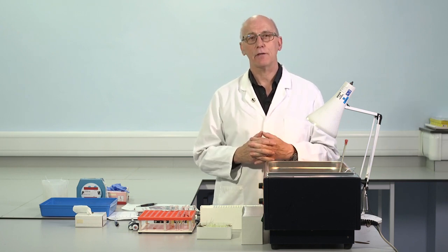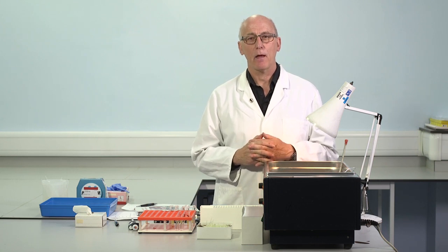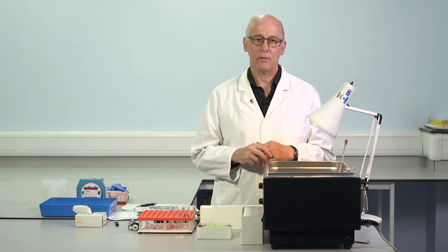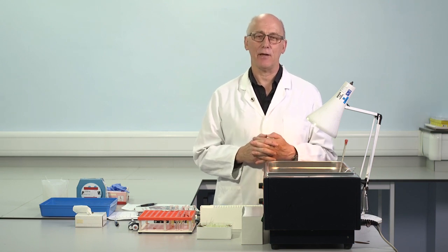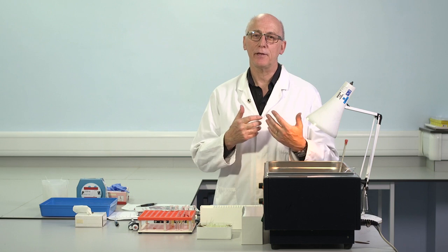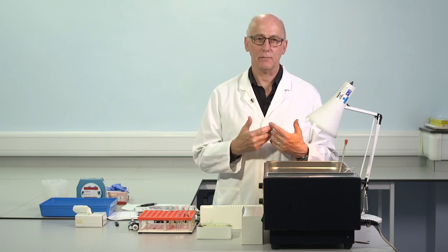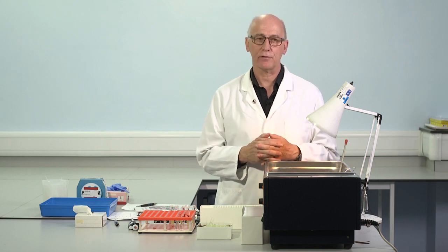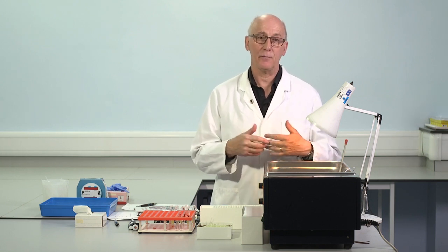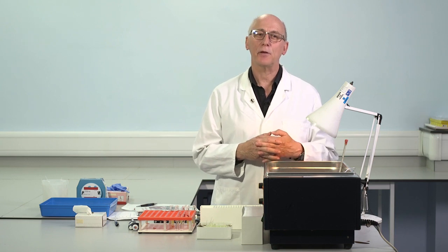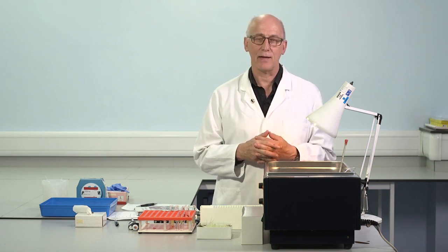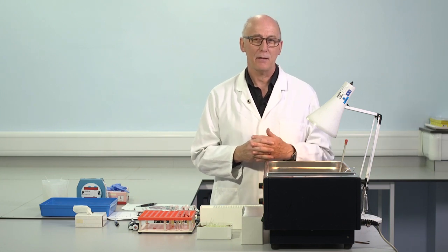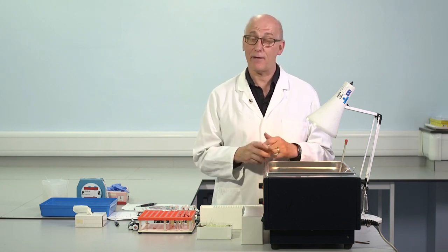They also have different activators, and there is a growing interest and focus on the activators present in aPTT reagents, particularly as we're beginning to see increased use of extended half-life products, factor 8 and factor 9, in development and beginning to be used, and it's becoming clear that the activator in aPTT reagent can have an important influence on the results which we obtain, particularly when we use that reagent in a factor 8 assay.